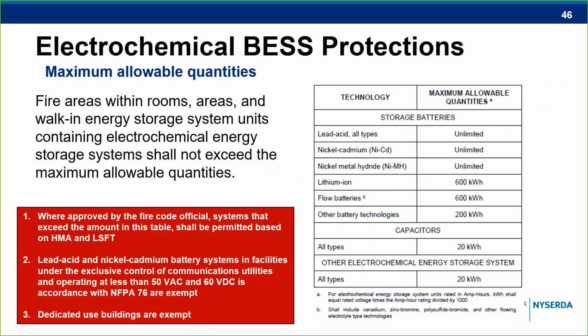Okay, so this slide here represents the maximum allowable quantities of batteries that can be installed in any given area. And if an installer wants to exceed the values listed in the table, it is possible, but they'll have to go through the hazard mitigation analysis and also that large-scale fire testing that keeps coming up to ensure that the system will be safe. And once again here, there are some other exceptions. Lead acid or nickel cadmium batteries under the control of communications utilities and also dedicated use buildings are exempt from this requirement.